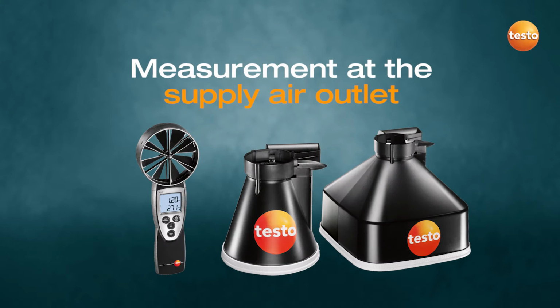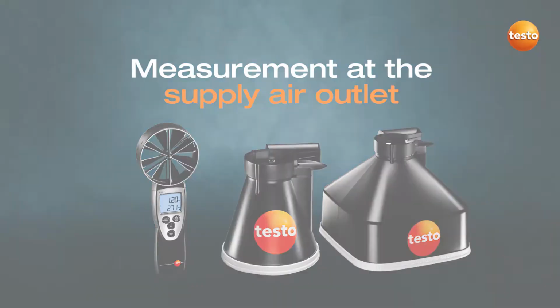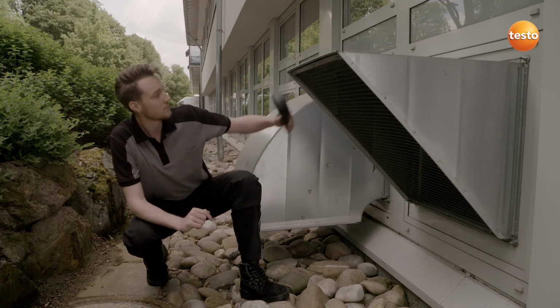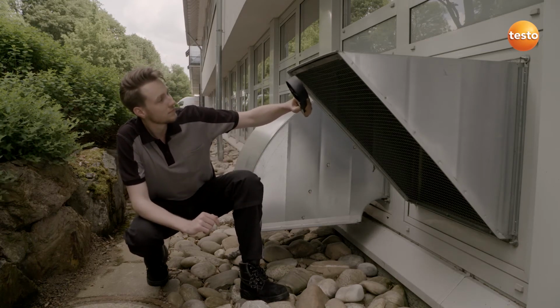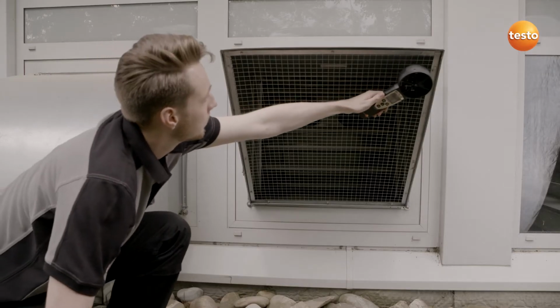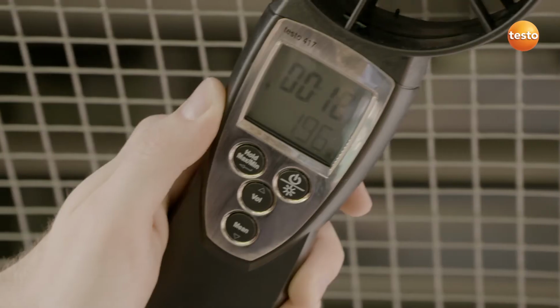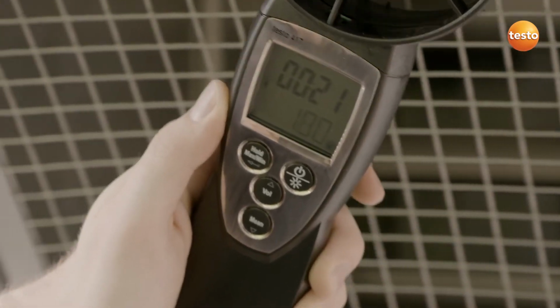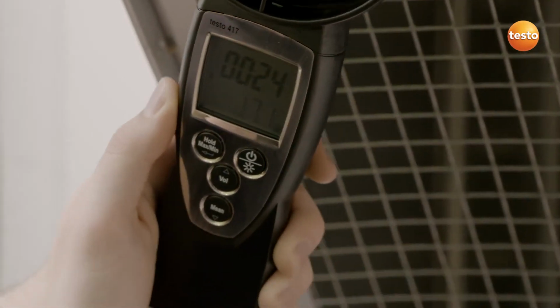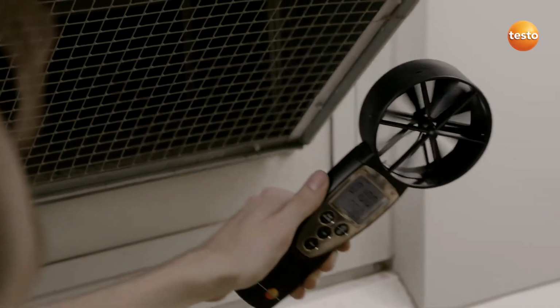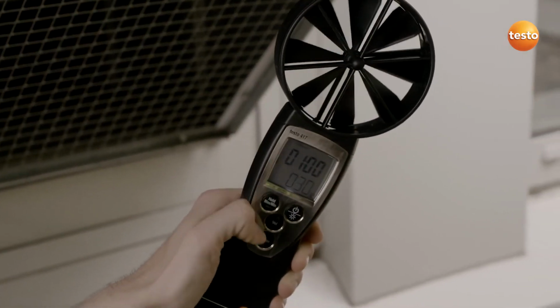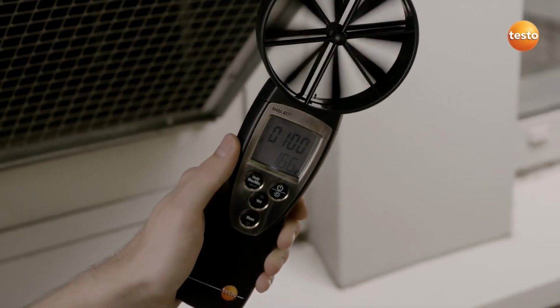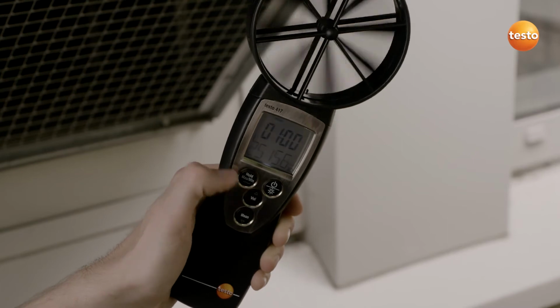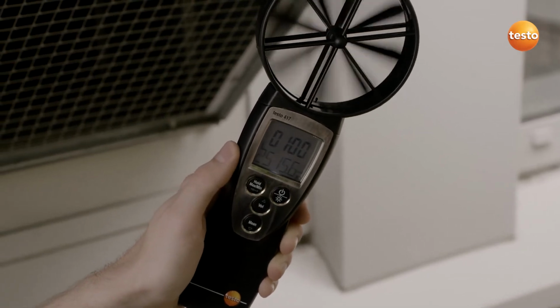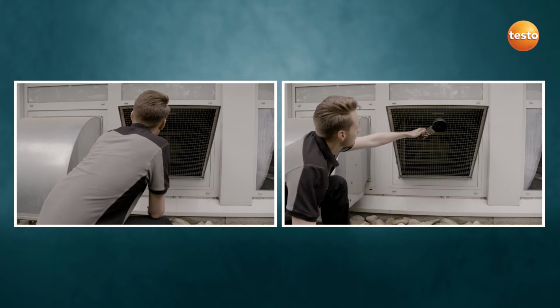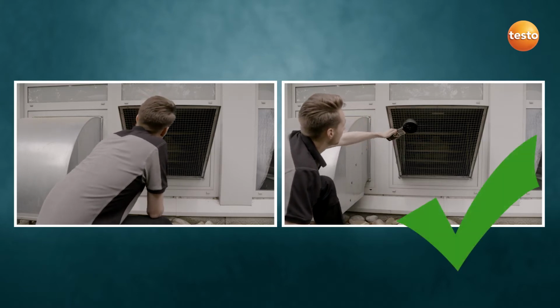This is how you measure properly at the supply air outlet. When measuring at the supply air outlets, take into account that different flow rates occur at the outlet area because of the air outlet grill. This is why the vane is moved across the ventilation grill in loops. The Testo 417 automatically generates a timed mean value. In the process, make sure not to block the air outlet unnecessarily, because any flow resistance affects the measurement result.